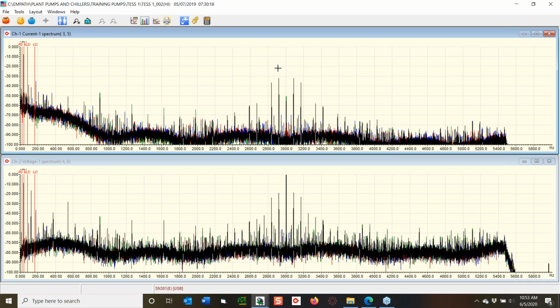Okay. And this is real data off of a 600 horsepower direct-on-line motor, other than the CT ratio of 3. I can come in here, and if I want to add in that kilowatt, I can. I don't at this point, but I usually use that to determine the severity of the fault, because when I go into linear and find a fault, that will give me the actual losses across that fault. And anything that's 10% of the total kilowatts is urgent. It'll vary from there depending on the application, but that's generally what I use.